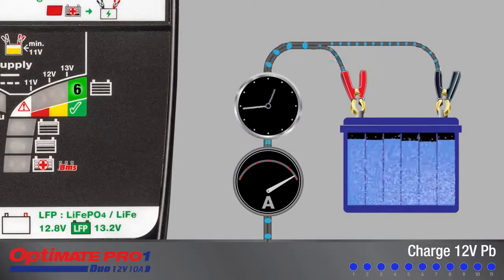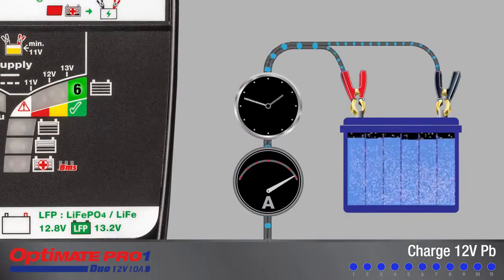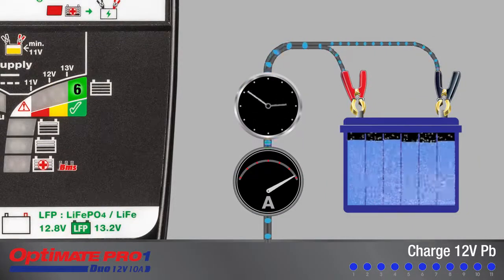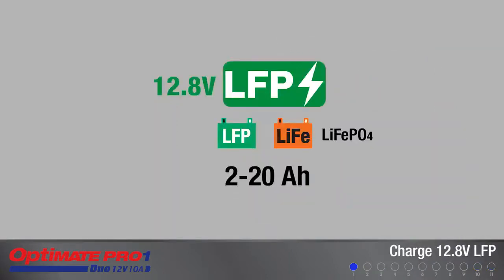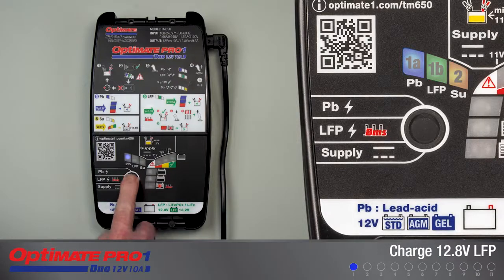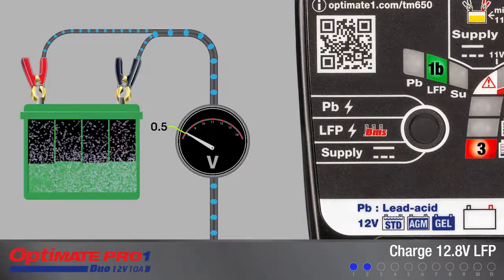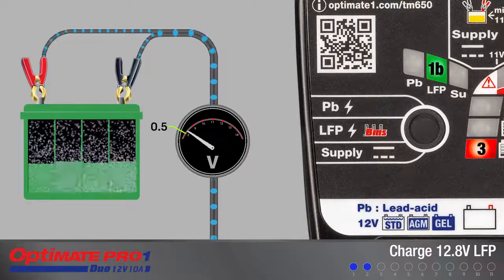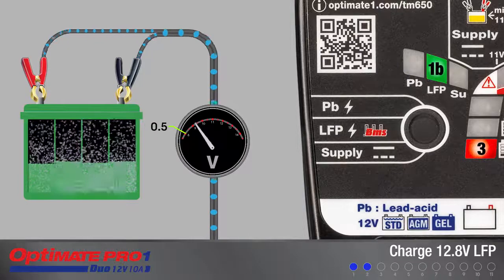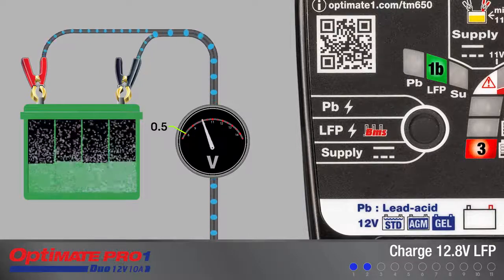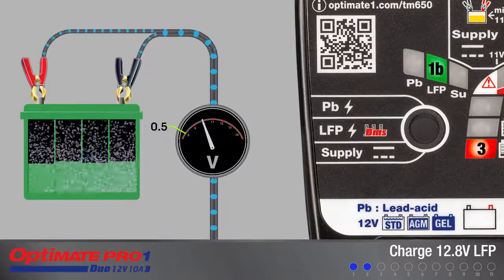After this, the 24/7 maintenance charge cycle continues until the battery is disconnected. For all 12.8-volt lithium iron phosphate batteries, select LFP charge mode. If the connected LFP battery's voltage is 0.5 volts or higher, charging continues automatically. LED 3 or 4 will turn on depending on the condition of the battery.